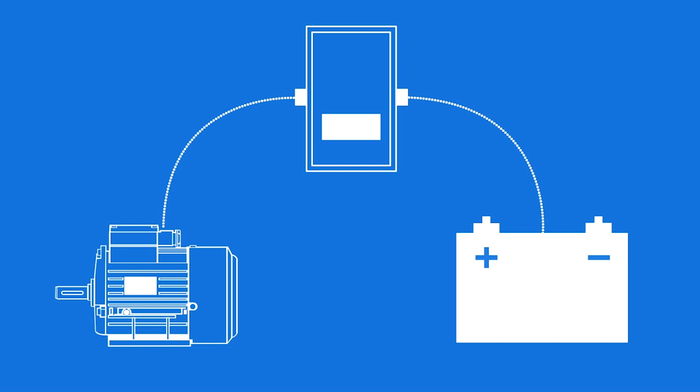When the switch is closed, a large amount of current flows into the winding causing a voltage to appear across the wire insulation. This voltage is due primarily to the inductance of the winding. The battery quickly discharges and the whole surge test is done in a few microseconds.